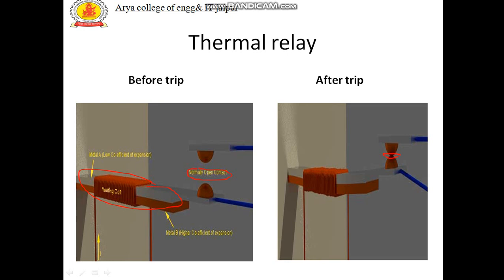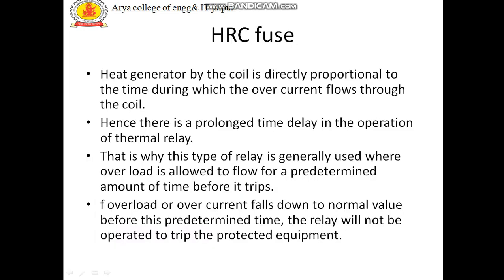The bimetallic element consists of two nickel alloy steel strips. These strips are highly heat sensitive and are free from thermal secondary effects from other sources. These relays are mostly used for protection of low voltage squirrel cage induction motors or DC motors. The limitation of such a relay is the short time overload withstand.